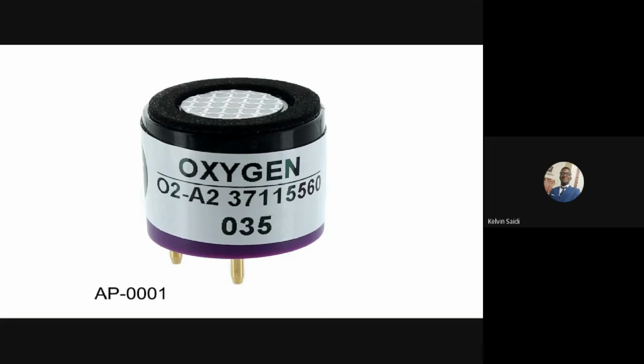There are two main disadvantages of these electrochemical sensors. The first one is that they rely on temperature very much. The process that I explained earlier, the reduction and the oxidation process, is temperature dependent. So if you have varying temperatures, this sensor misbehaves, and you can get inaccurate readings at some point. And according to the sensor design, the chemical reaction will slow down eventually, and it will require constant calibration, and it has a shorter lifespan. So that's another disadvantage of electrochemical sensors.